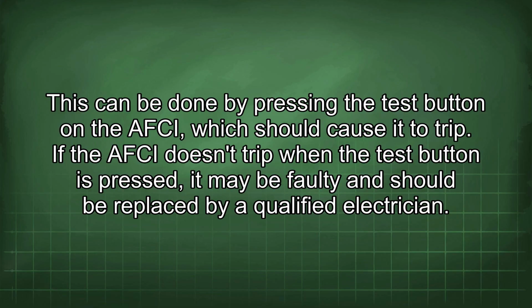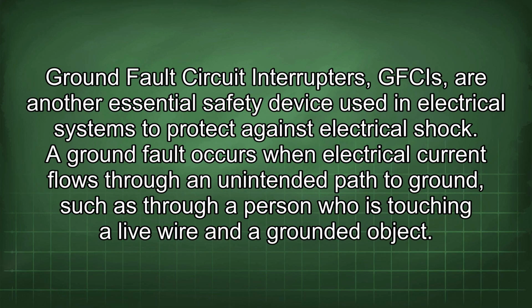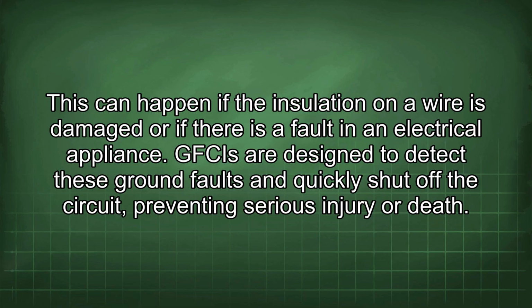Ground fault circuit interrupters, GFCIs, are another essential safety device used in electrical systems to protect against electrical shock. A ground fault occurs when electrical current flows through an unintended path to ground, such as through a person who is touching a live wire and a grounded object. This can happen if the insulation on a wire is damaged or if there is a fault in an electrical appliance. GFCIs are designed to detect these ground faults and quickly shut off the circuit, preventing serious injury or death.